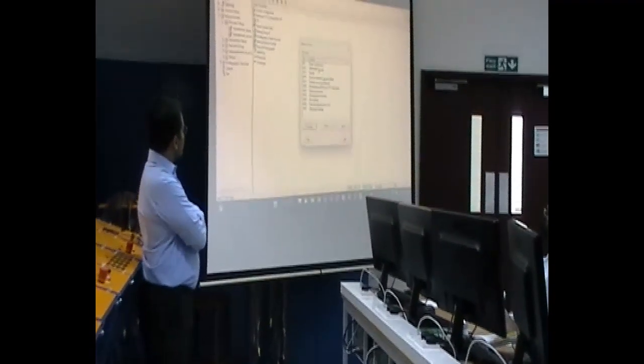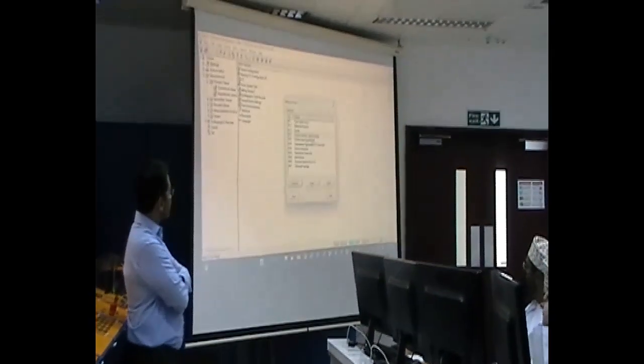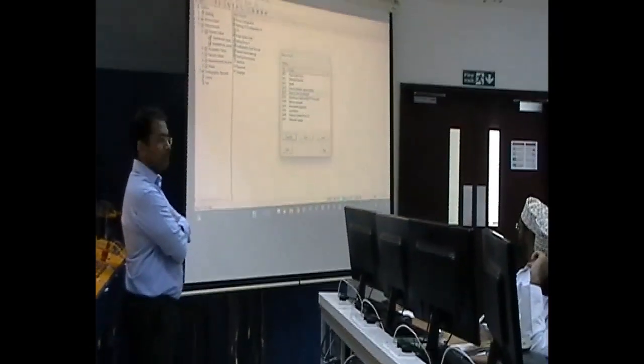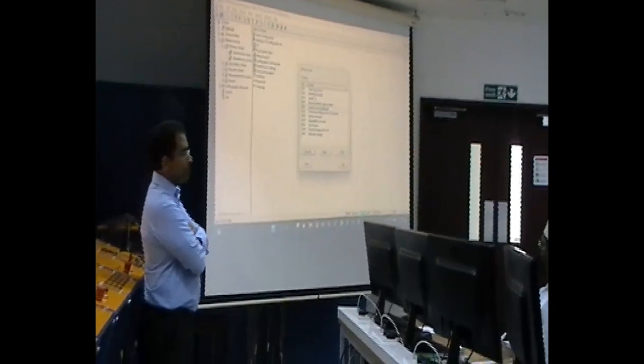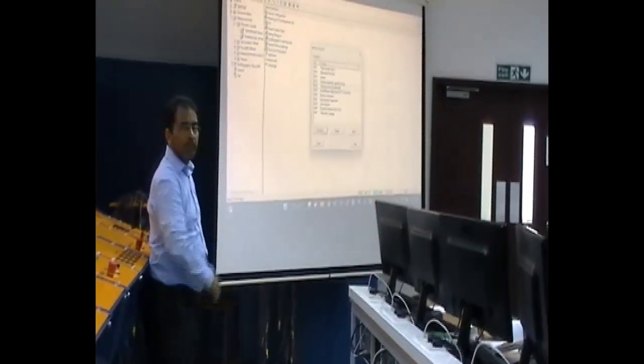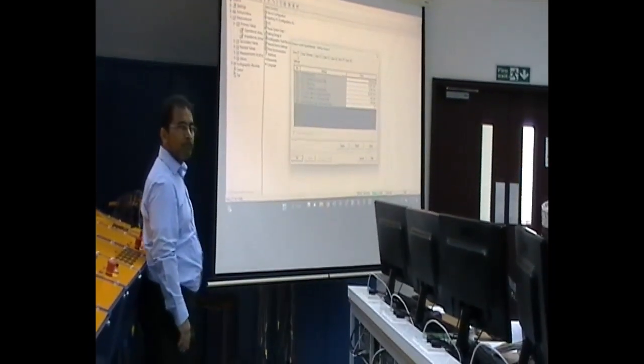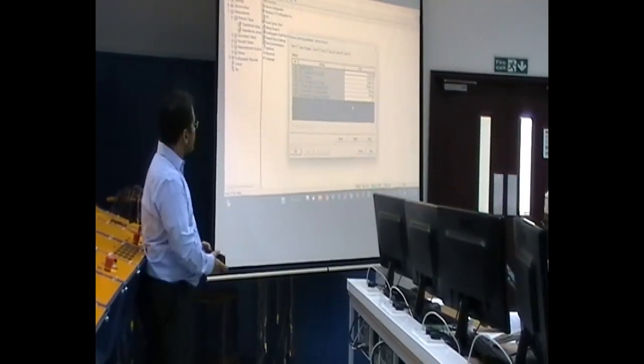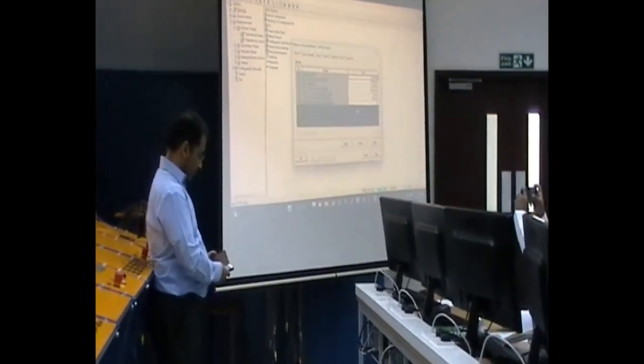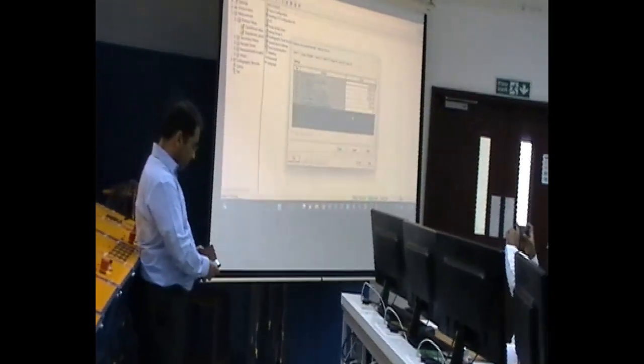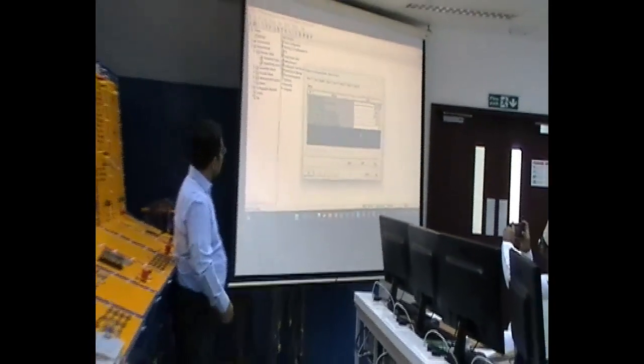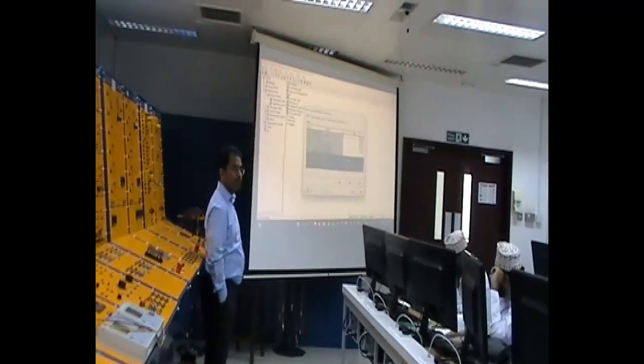And here I have the setting of the distance relay, so I'll go through the setting and whatever differential or any other relay that is enabled. For example, distance relay, I have zone 1 setting, and in the table you need to decide the distance relay characteristic. What was the characteristic which we selected already from the beginning? Quad.